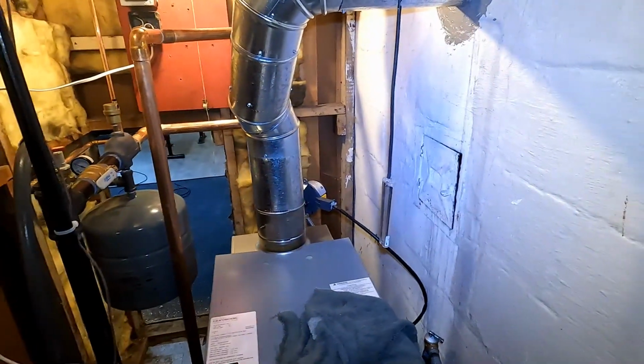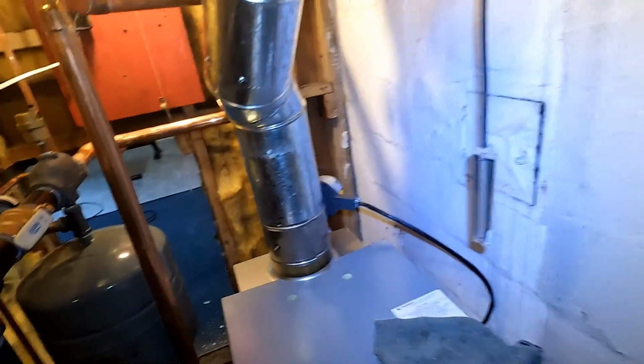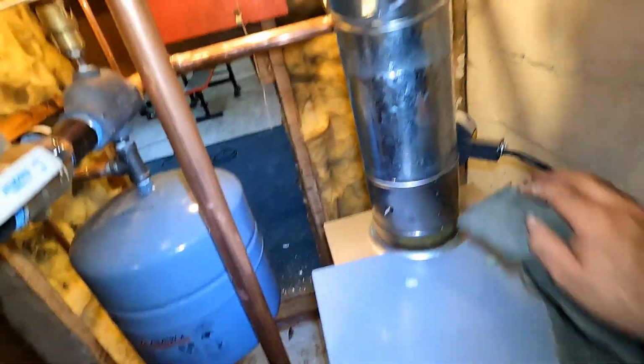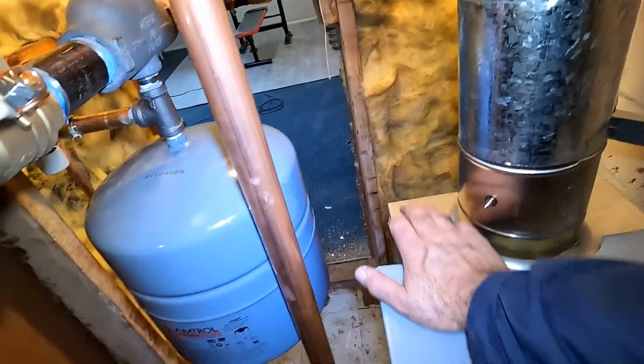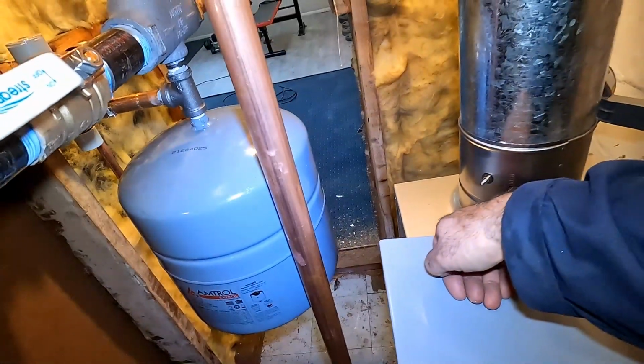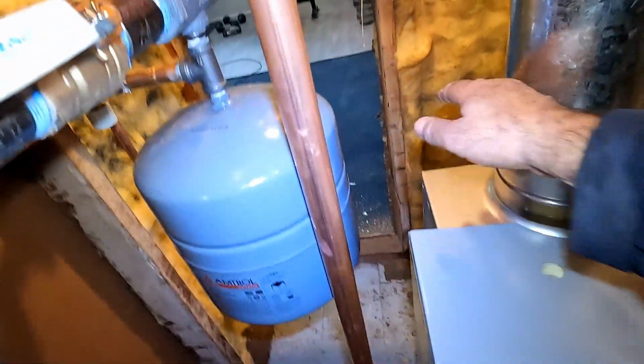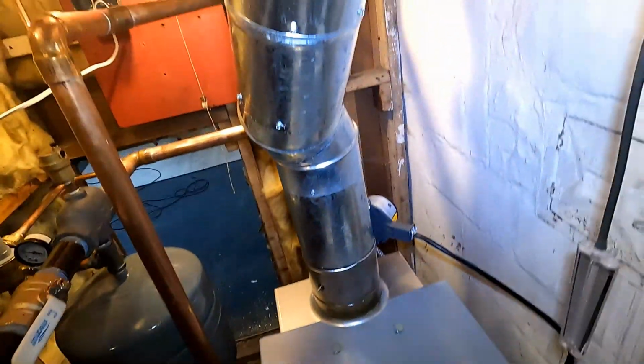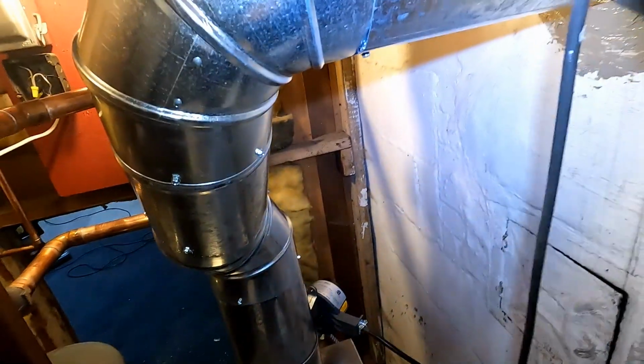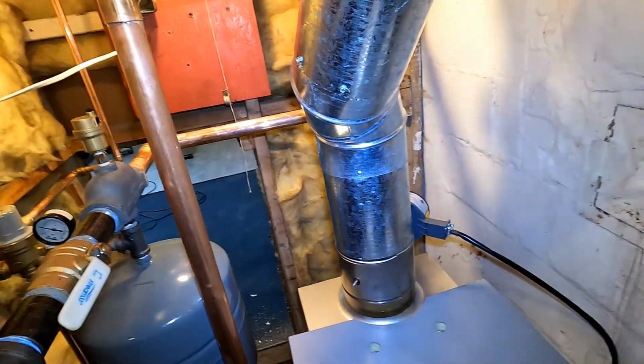You can see I have my draft gauge in there. So I'm going to refresh this again. This is the draft box. When you do a combustion analysis, you take it down here before the dilution air. Dilution air gets in here, and then your draft measurement is taken over here after the dilution air gets in.